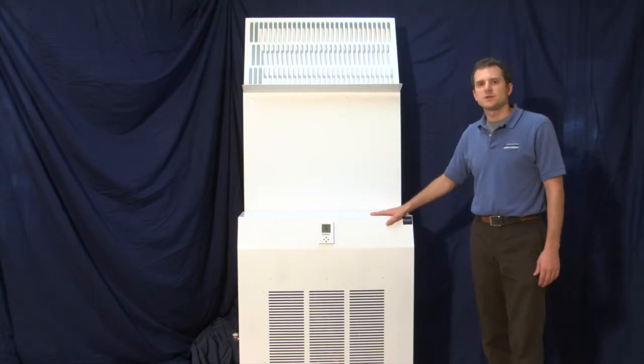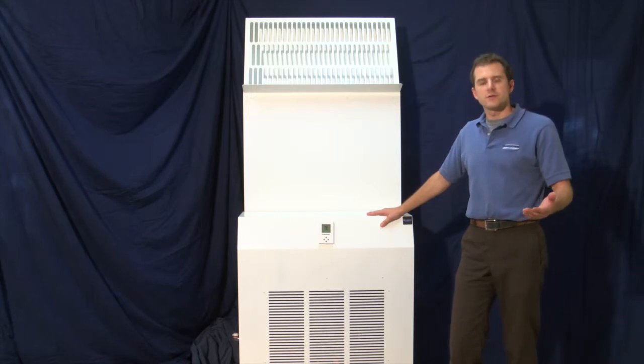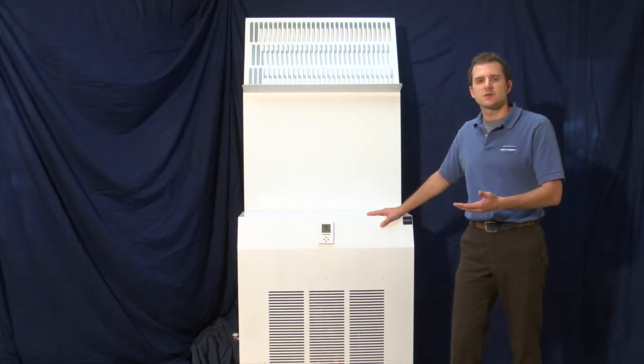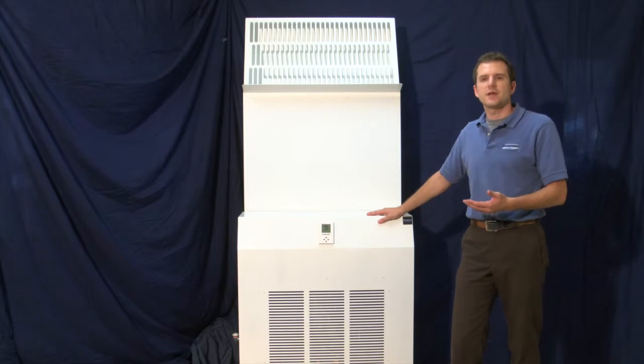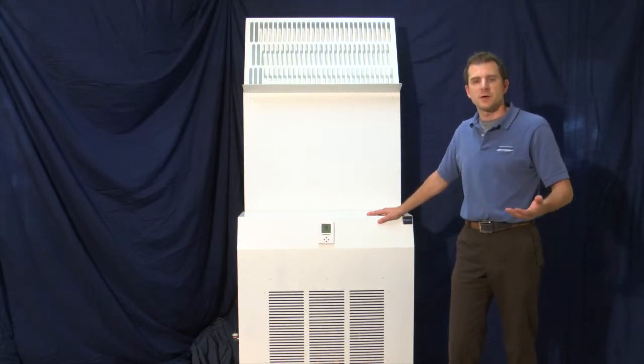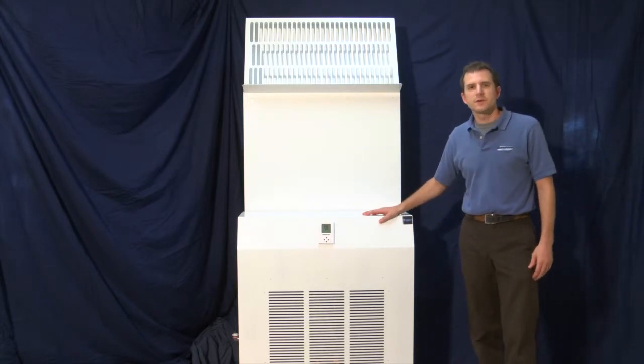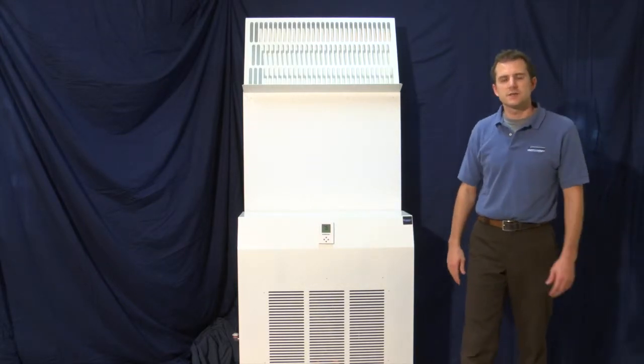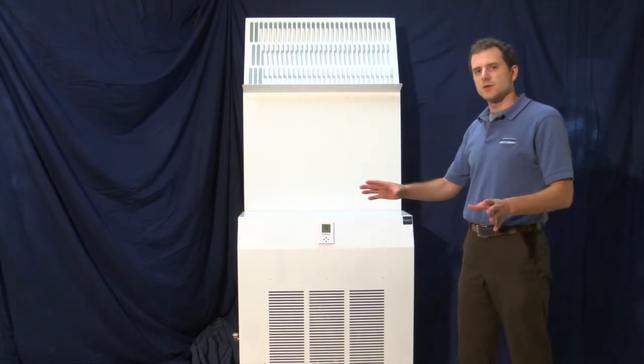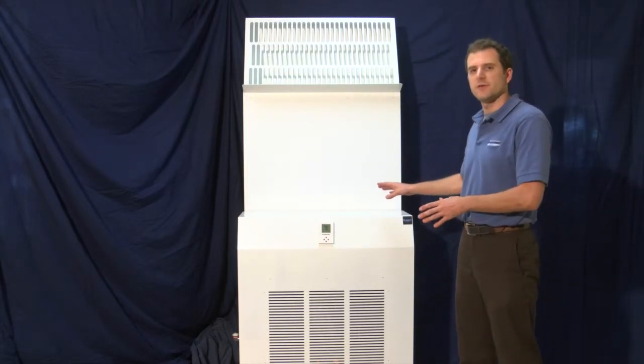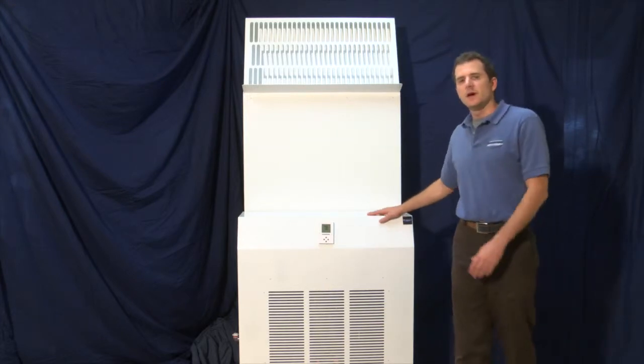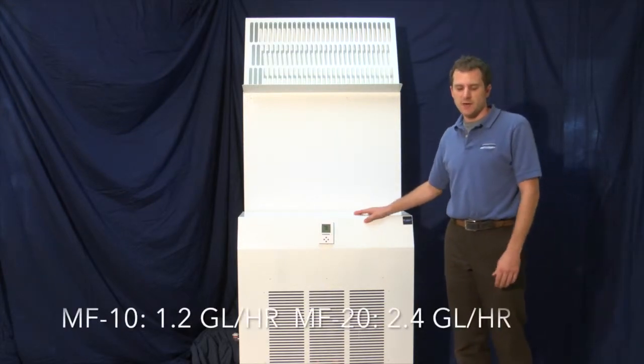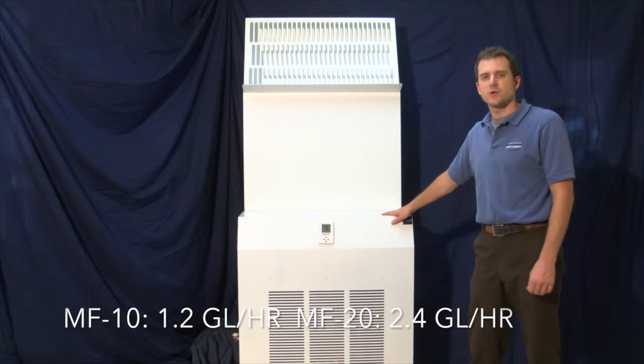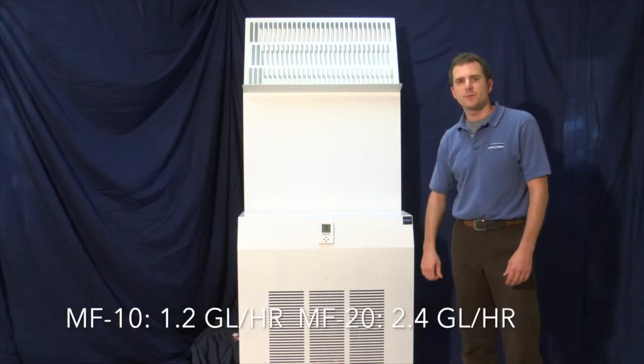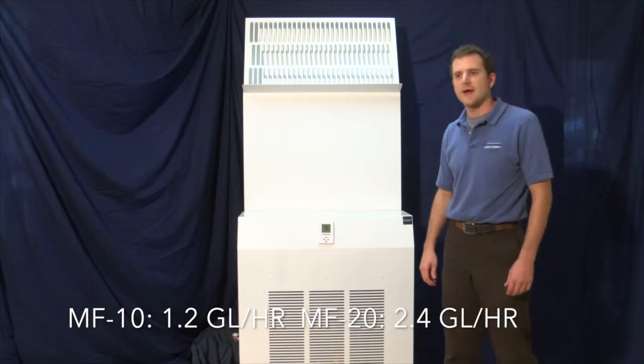Generally, the factory recommends treated water, an RO, reverse osmosis, or DI, deionized water source. Although there are certain applications with heavy organics in the air where treated water can harm you as much as help you. The most important things to think about when choosing an RO or DI system is that the water treatment system can properly feed the humidifier with the right amount of water. The Mist-Free 10 is doing 10 pounds per hour, or about 1.2 gallons per hour. The Mist-Free 20 is doing 20 pounds per hour, or about 2.4 gallons per hour.